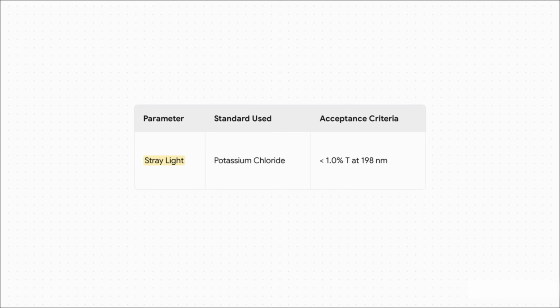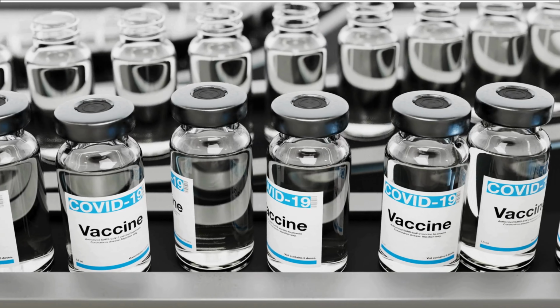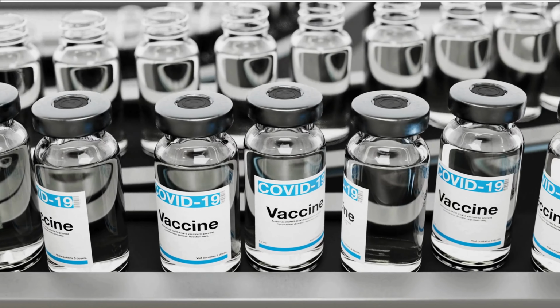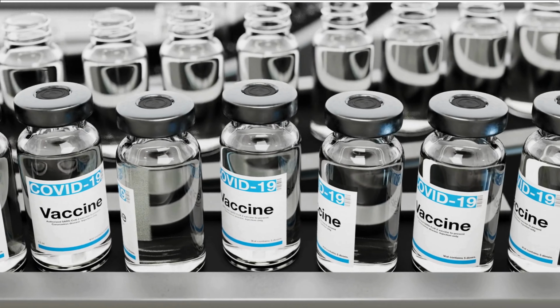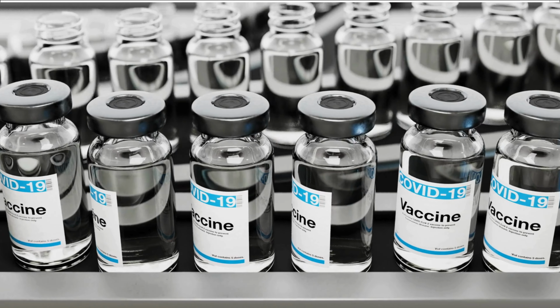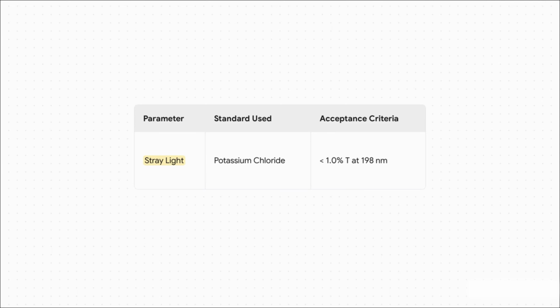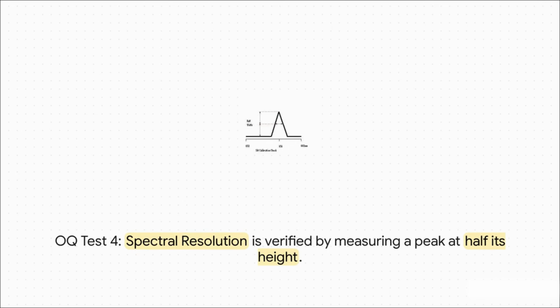All right, next up, we have to tackle something called stray light. This is basically unwanted light, like noise, that can hit the detector and mess up the reading. To test for it, we use a solution that should block all light at a specific wavelength, and we make sure that less than 1% of any junk light is getting through. It's kind of like soundproofing a recording studio to get a perfectly clean track. And finally, there's spectral resolution.